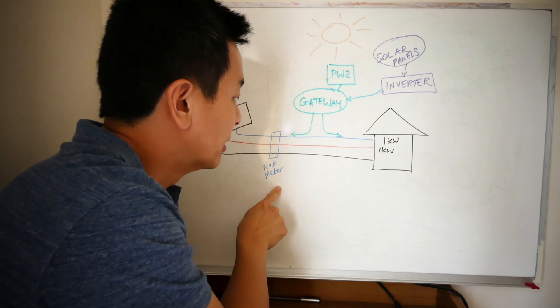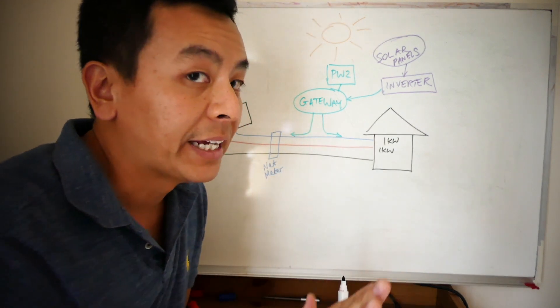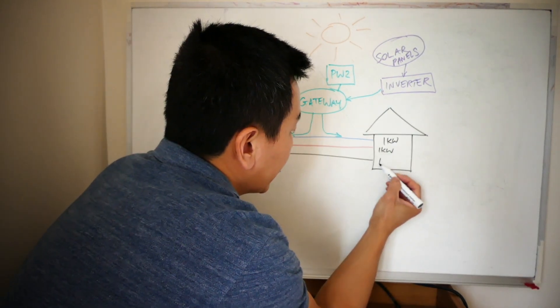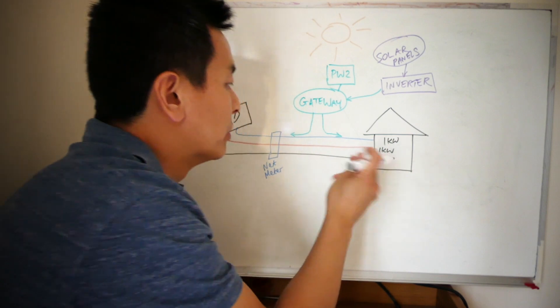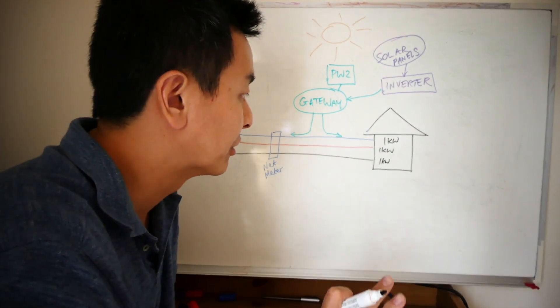And the net meter then goes, 'Okay, I've given you one and we're going to take one back.' That cancels each other out; it doesn't bill the customer. Same thing applies if it has a load on this black phase as well: sends one from the grid, takes one back from the gateway, cancels each other out.